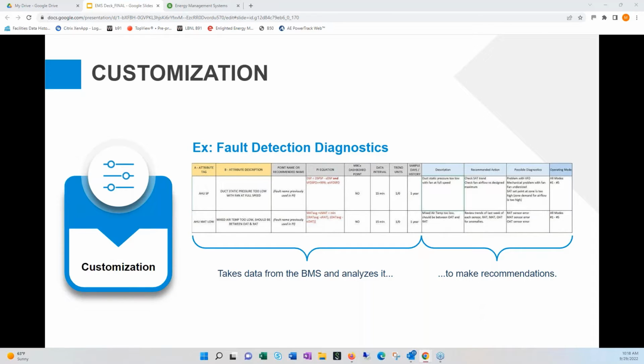The recommended action here says to go look at the trends of the data for at least a week, checking the return air, mixed air, and outside air sensors for anomalies. When you do that, you'll likely find out which sensor is the problem. So the diagnostic is probably a bad sensor, but which one? Before even stepping into the field, if you take that recommended action and look at the data, you can probably figure out which one it is.